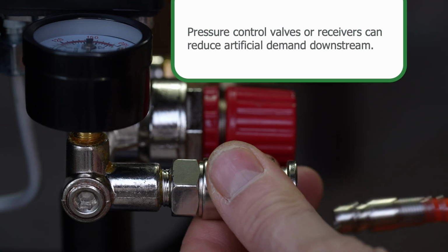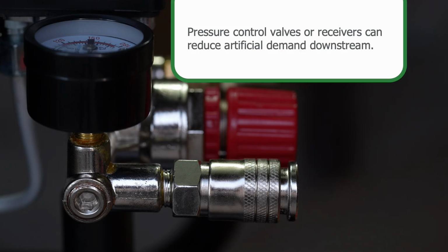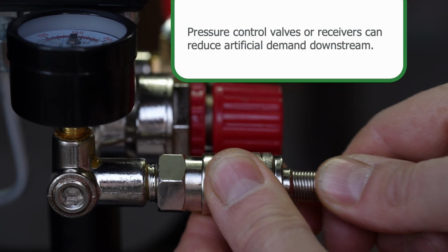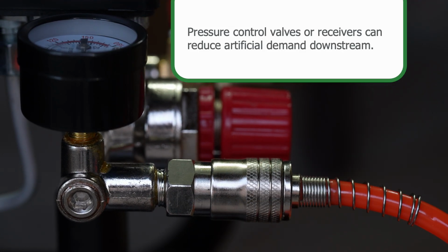Reducing pressure at end uses using pressure control valves or storage receivers does not impact how hard the compressor has to work to compress the air, since it doesn't change the discharge pressure, but it does reduce artificial demand downstream of the pressure reduction.